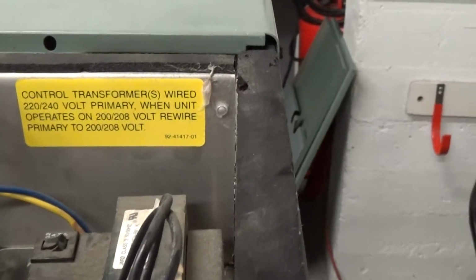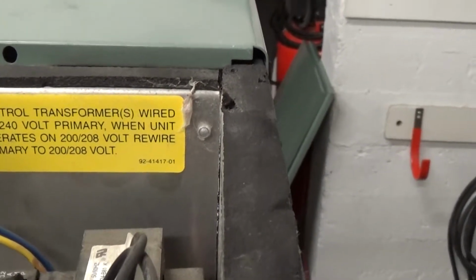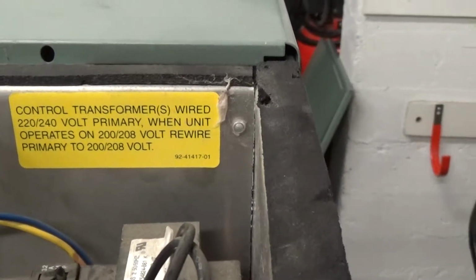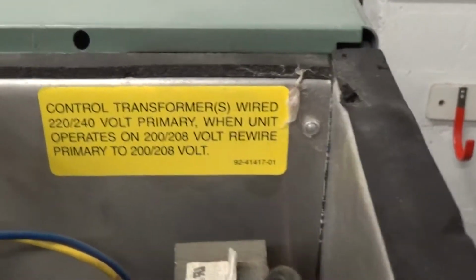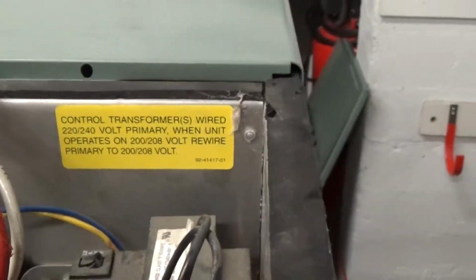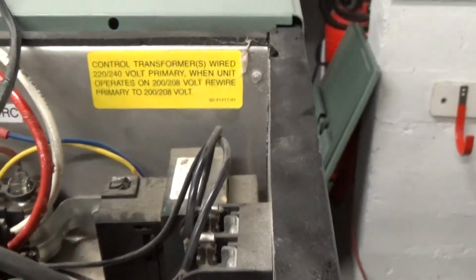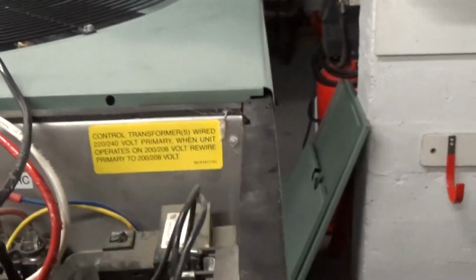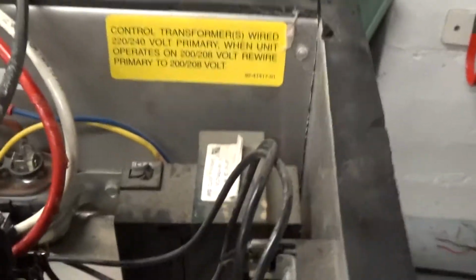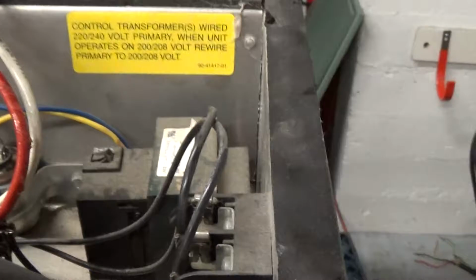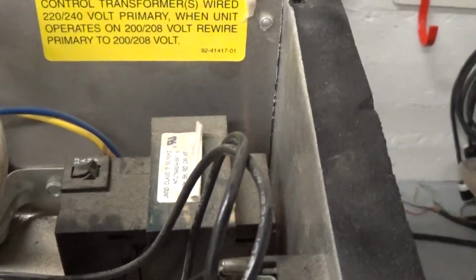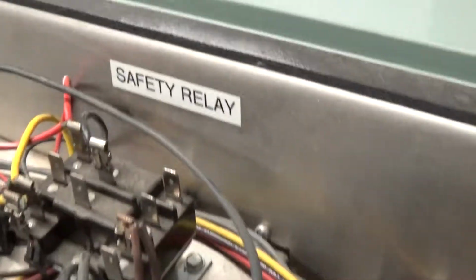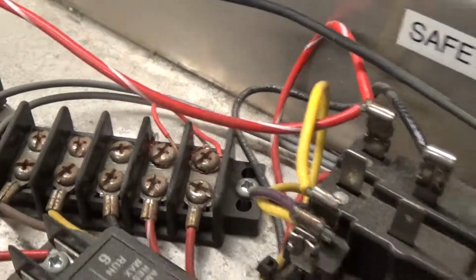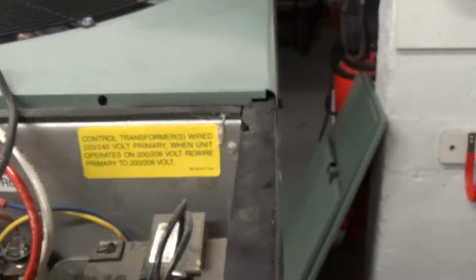The control transformer gives you the option of 220, 240 volt or 200, 208 volt for incoming power. It leaves here wired for 220, 240 volt. It can make a slight difference sometimes if you have lower voltage in your plant, meaning 200 or 208, in which case you just want to change two of the wires on the primary side of that transformer. The unit leaves intentionally with a little jumper there. You see that red jumper? That's actually an option if you want to set up for remote on-off start.